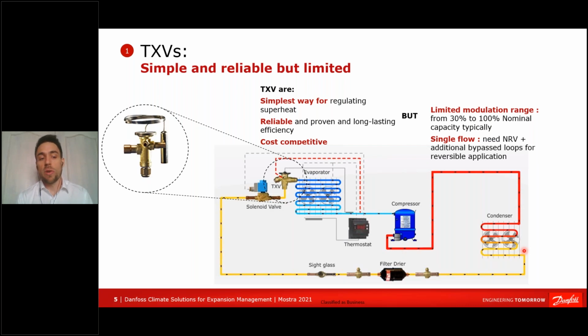The modulation range is limited to 30% to 100%. That may be enough for many applications, but not enough for a lot of variable speed applications — I'll insist on this later. It's also a single flow solution, meaning if you want a reversible chiller, you have to double the number of thermostatic valves, add check valves, and so on, complexifying the system you're building.